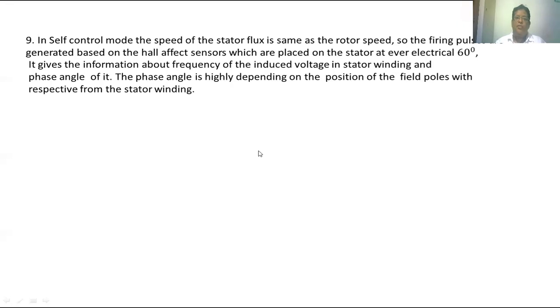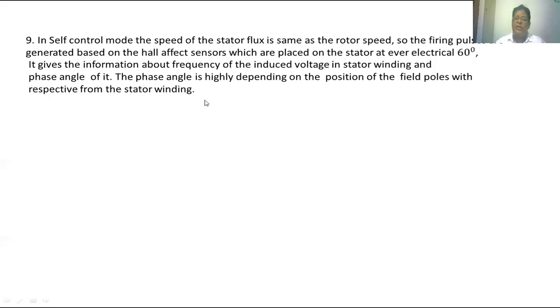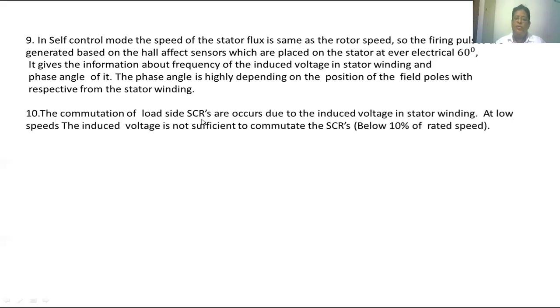In self-controlled mode, the speed of the stator flux is the same as the rotor speed. The firing pulses are based on Hall effect sensors which are placed on the stator at every 60 degrees. These sensors give information about the frequency of the induced voltage and the phase angle of the stator winding. The phase angle is highly dependent upon the position of the field pole with respect to the stator winding. The commutation of load side SCRs occurs due to the induced voltage in the stator winding.